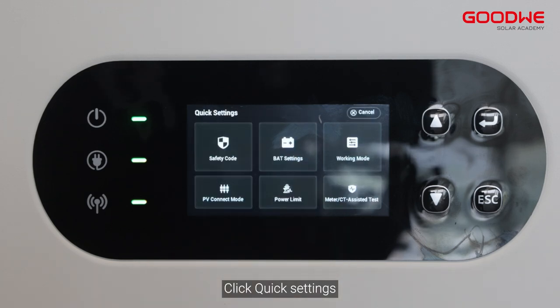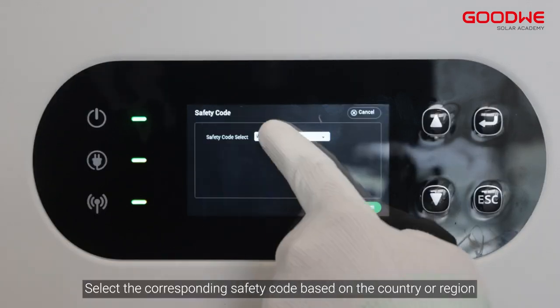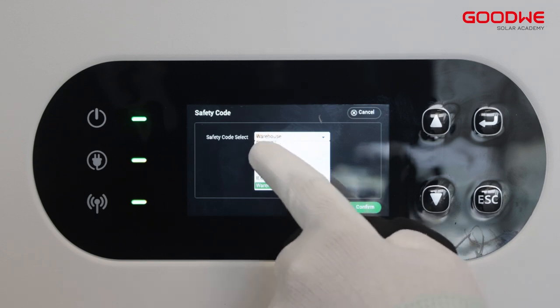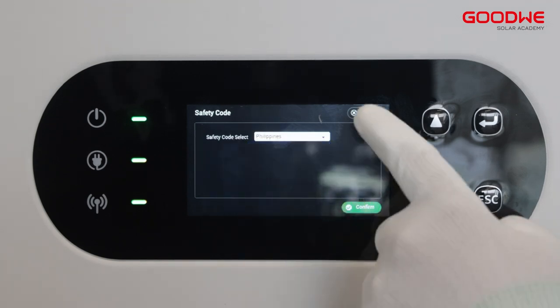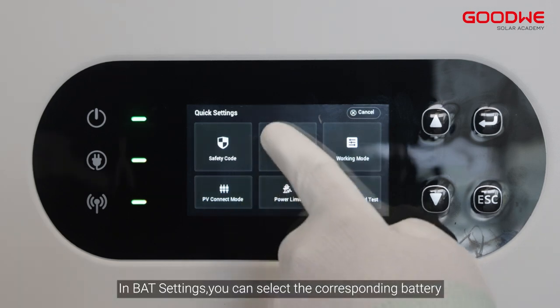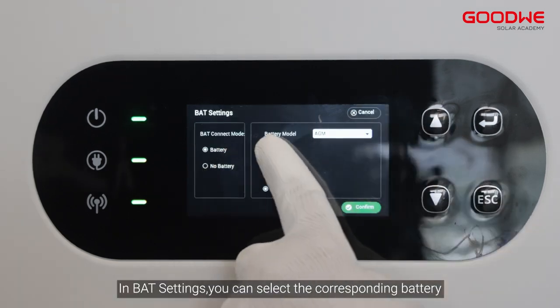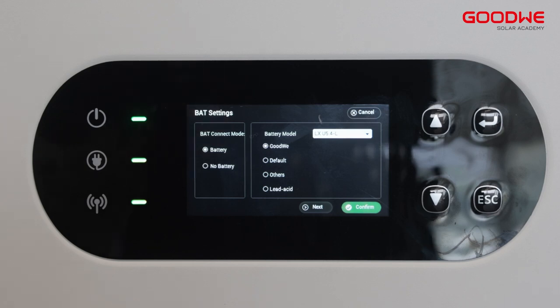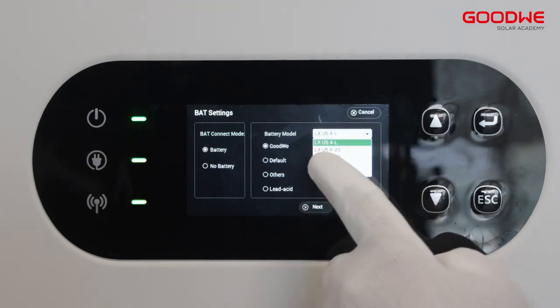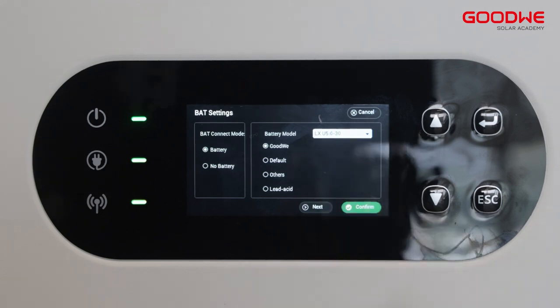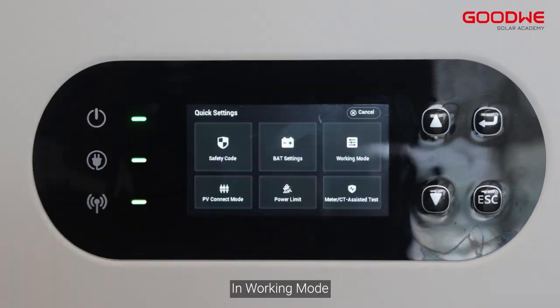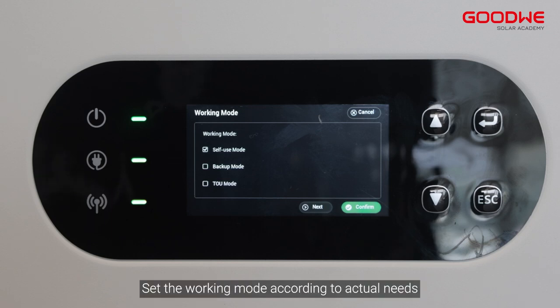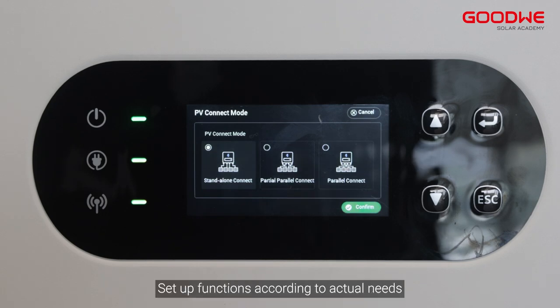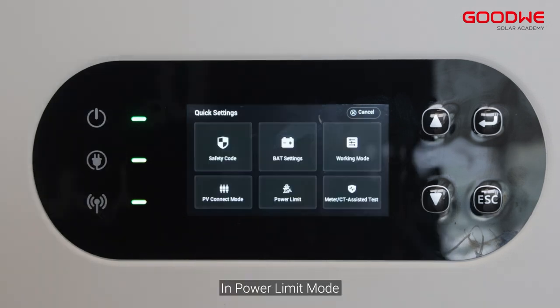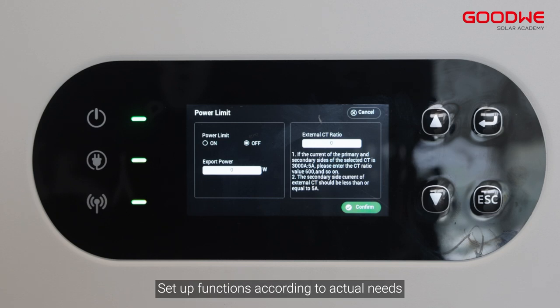Click Quick Settings. In Safety Code, select the corresponding safety code based on the country or region. In BAT settings, you can select the corresponding battery. In working mode, set the working mode according to actual needs. In PV Connect Mode, set up functions according to actual needs. In power limit mode, set up functions according to actual needs.